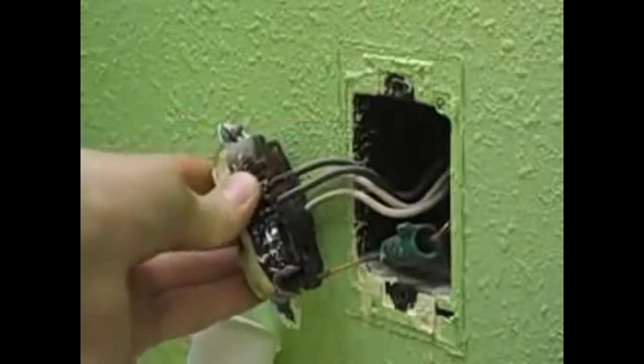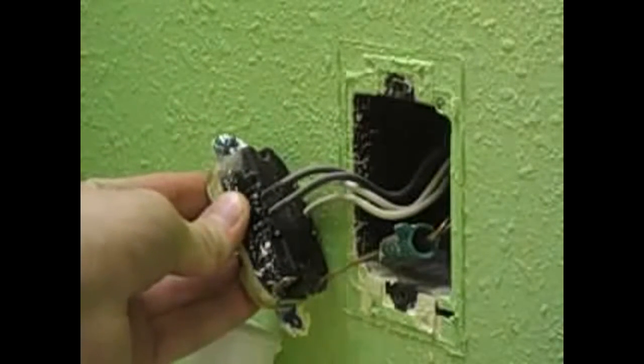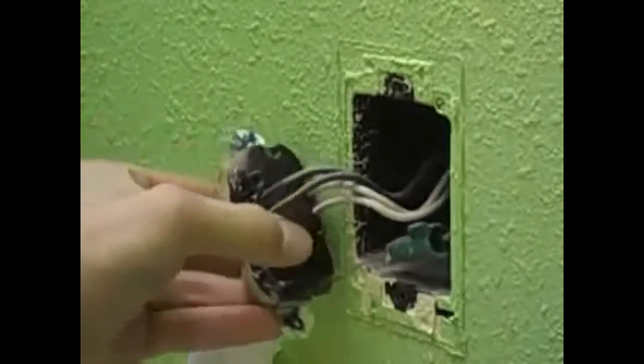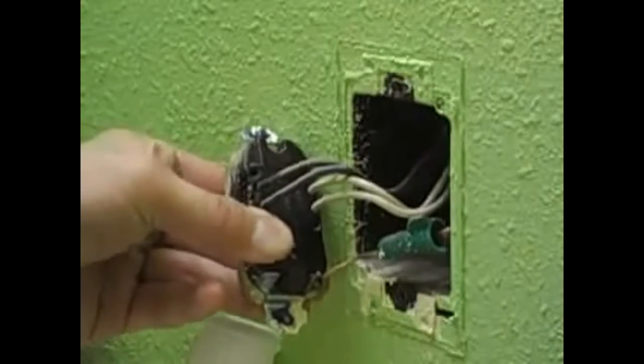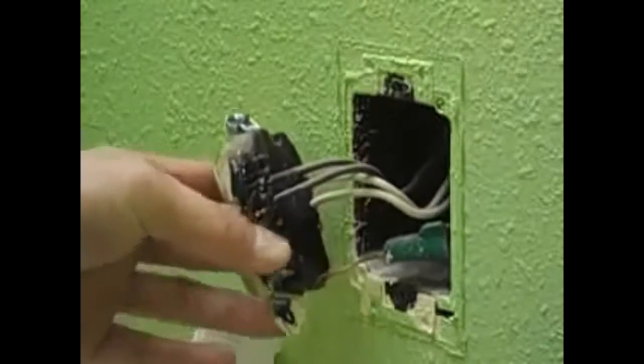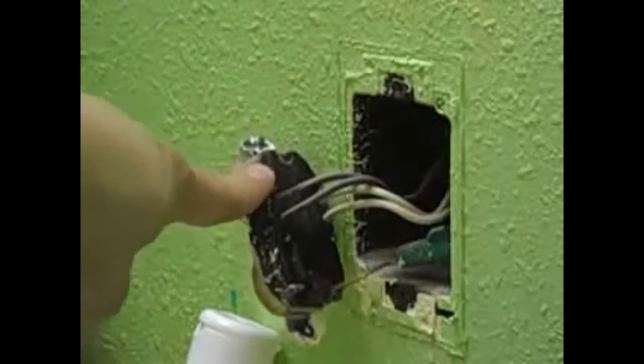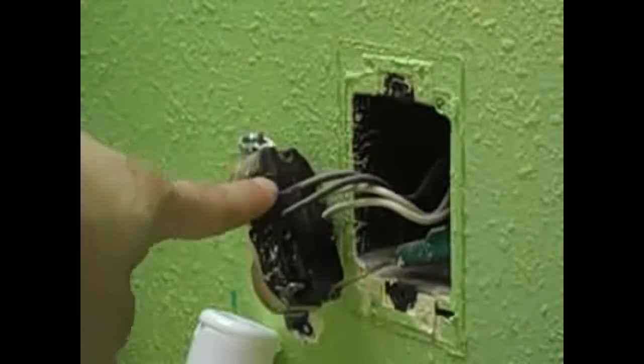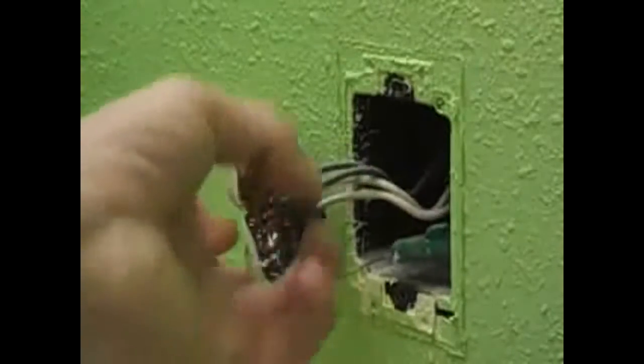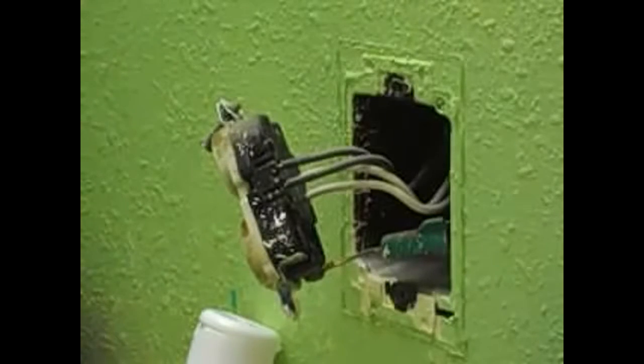They're stabbed into the back of the outlet. On some outlets, probably not this one—yeah, not on this one—but the newer ones will have a place where you can insert a flathead screwdriver and pull these wires out. But we didn't get that luck today with this outlet, so what you're going to want to do is take your wire cutters and just snip those off.